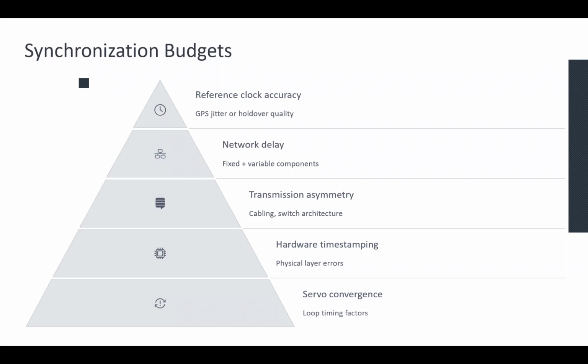Another aspect involves hardware time stamping capabilities. If the physical network interface card or measurement does not support precise hardware-level time stamping, then software-level delays can introduce errors in the microsecond range into the system. In high performance systems like synchrophasor networks or telecom base stations, this alone can basically determine whether the system meets a certain class of synchronization accuracy or not.